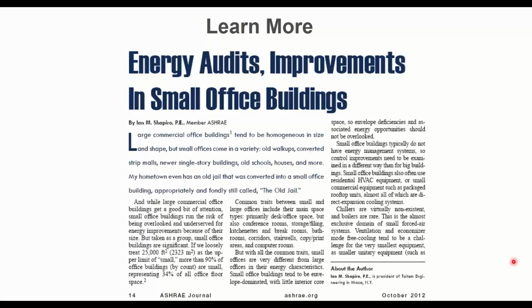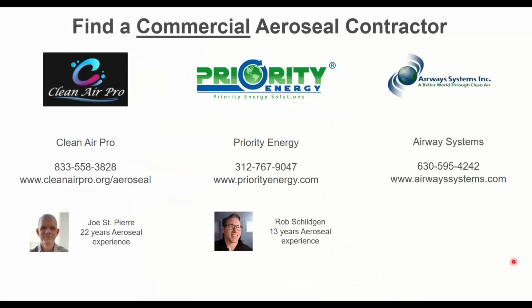If you're thinking about doing this for your own building, you can certainly contact me and I'll get you in touch with the right folks. But these are the right folks. These are the three companies that are doing commercial Aeroseal in the Chicagoland area. There's like 30 or 40 of them doing it residentially. But to do it commercially, you need more equipment. Hence, it's a bigger startup cost. You need more expertise and bigger crews. So not everybody is doing commercial. Most companies are doing residential and then what I'm going to call light commercial, like you got a small office building with a 5-6 ton system. Those guys would be able to do that. But if you got a big building with large systems, these are the guys you'd want to talk to.